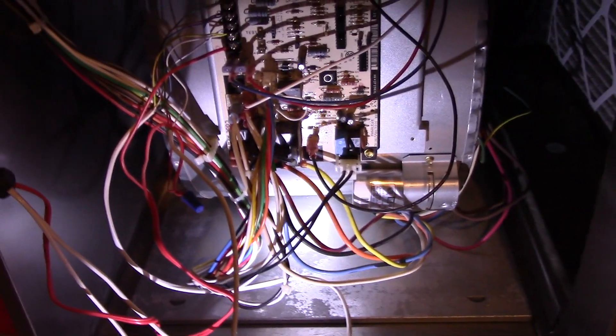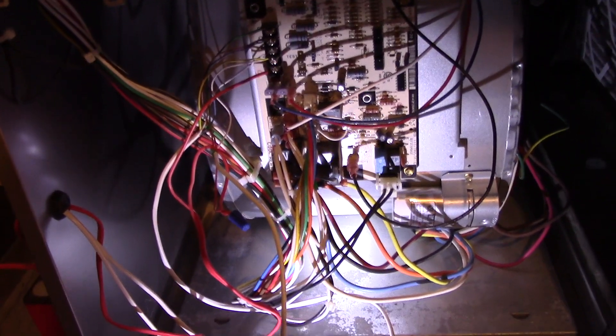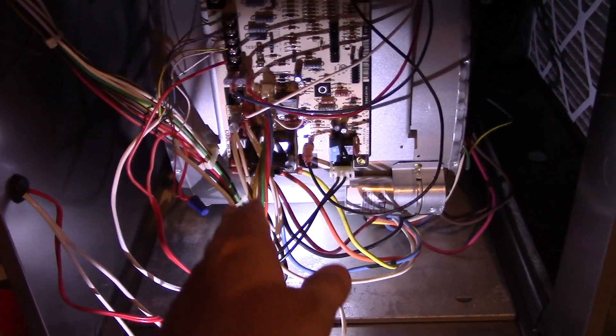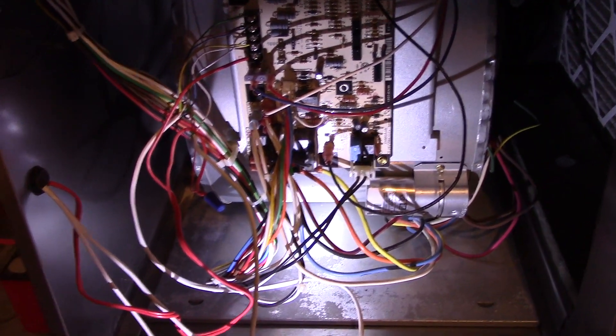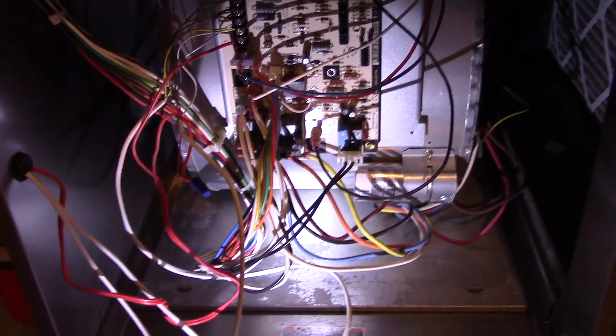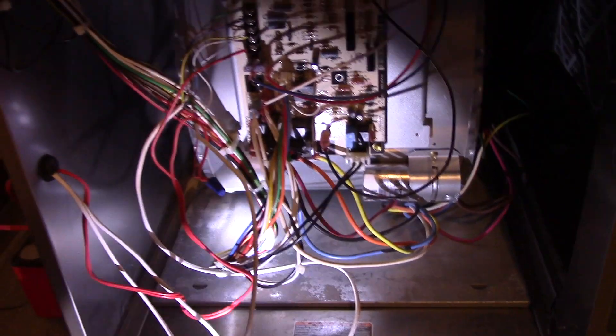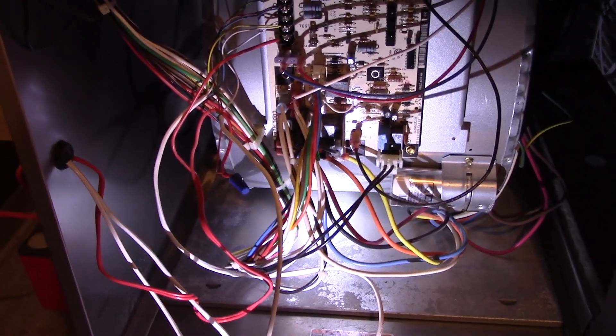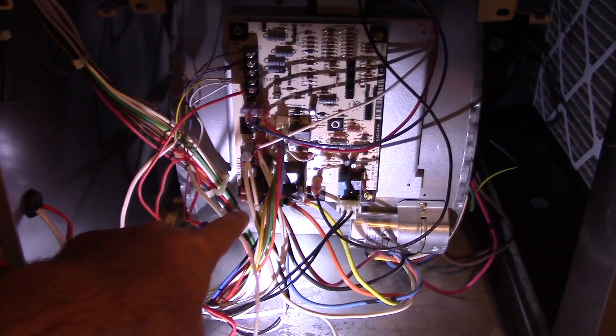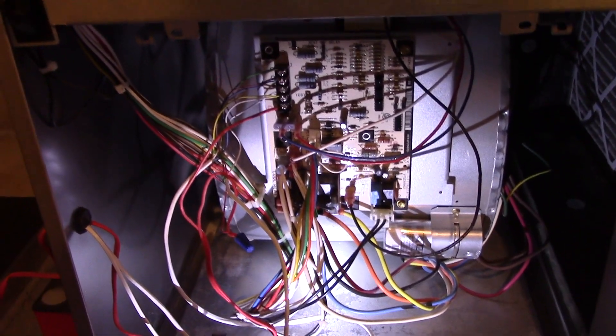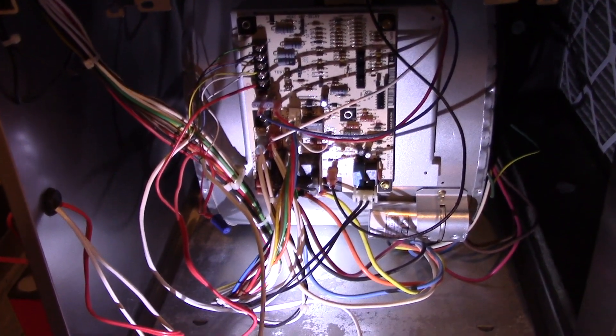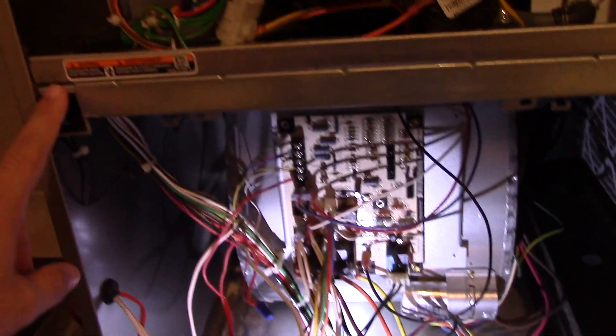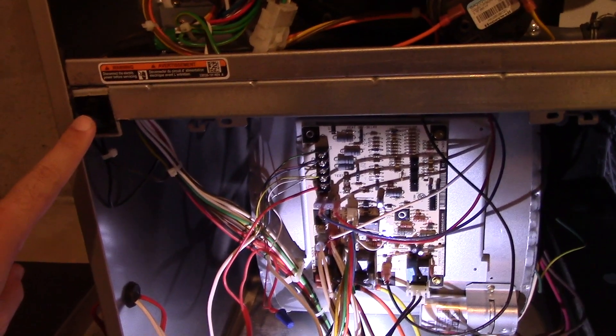Make sure everything is all clear, and make sure your hands are not inside there when you power this up. So first things first, go to your thermostat and put it on fan mode. Basically, put your fan switch from auto to on, so we'll use the heat speed. What you're going to do is listen between the two speeds that you want and just listen to how the blower sounds when it comes on. Right now I have the thermostat upstairs set to fan on, and I have it back on the blue wire, which is medium-low. So let's listen to how the blower sounds on the blue wire. We're going to push in the switch, and let's listen.